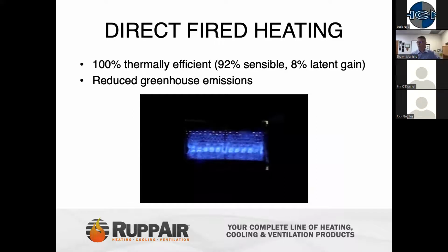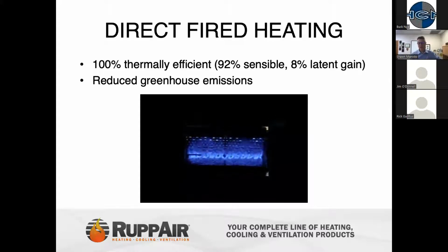The other big benefit over indirect fired systems is having that 100% thermal efficiency. We're going to be about 92% sensible heating capability with 8% being latent gain. The idea behind direct fired as well is an overall reduction of greenhouse emissions. Because you're utilizing all that heat to heat the space, you can get by with firing at lower BTUs, rather than with indirect fired, where some of those BTUs go out into the atmosphere.